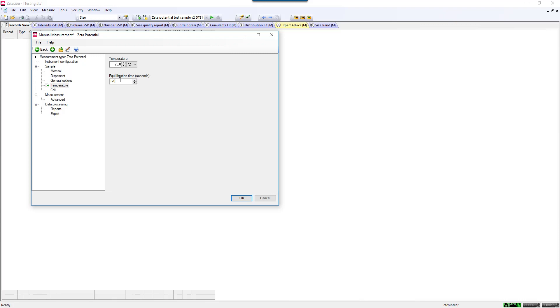For example, if you took your sample out of a freezer, filled the cuvette, and you would like to make a measurement at a much higher temperature, maybe 30 or 40 C, you would need to build in a couple minutes of equilibration time just to make sure your sample comes to the temperature of the instrument for the measurement.